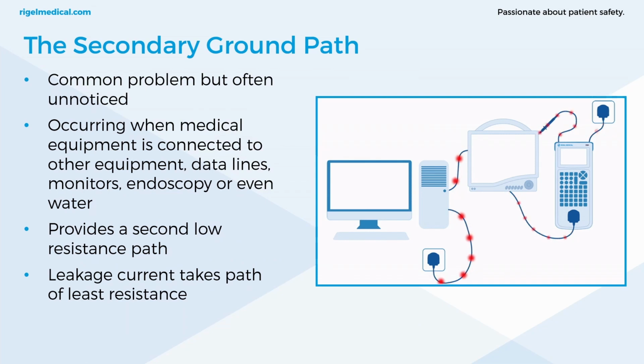Just using an example. So the secondary ground path is a common problem, but often unnoticed. It occurs when medical equipment is connected to other equipment. This could be data lines, monitors, endoscopy, or water. We know that current takes the path of least resistance, and the image represents an example of a secondary ground connection via a data cable on a PC.